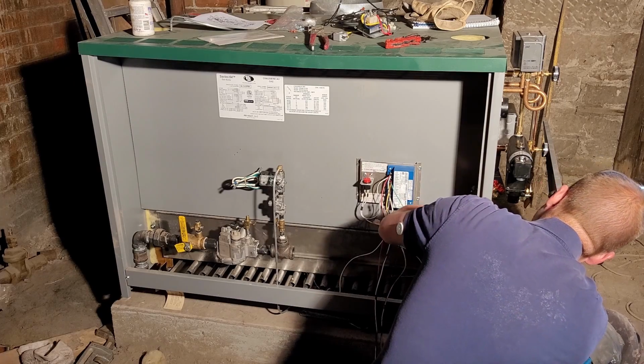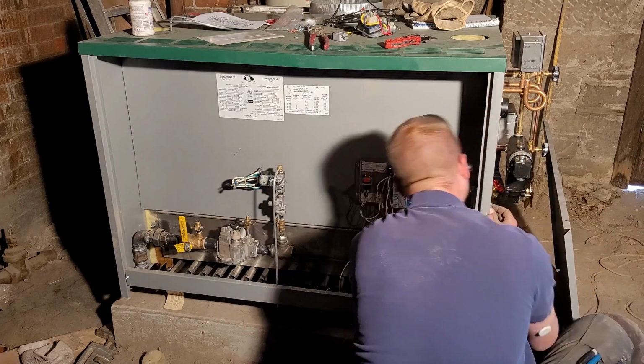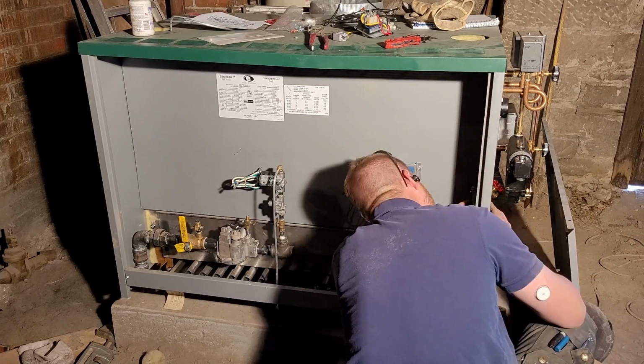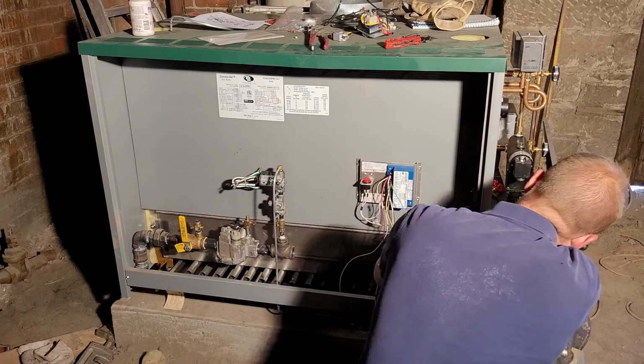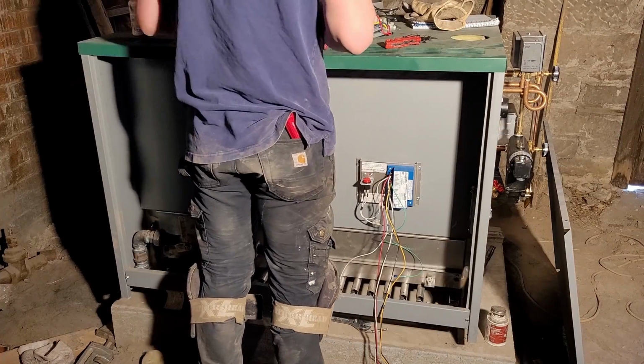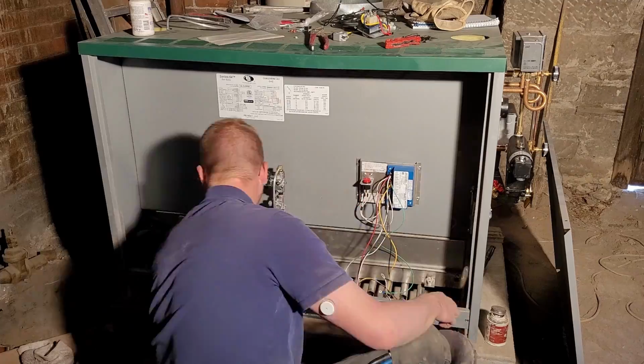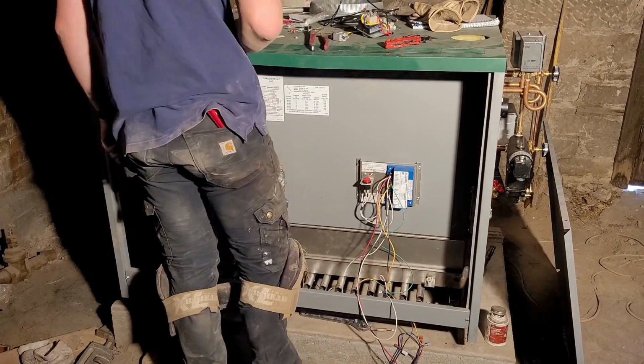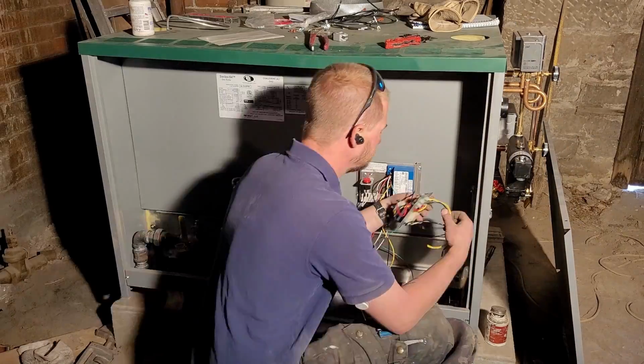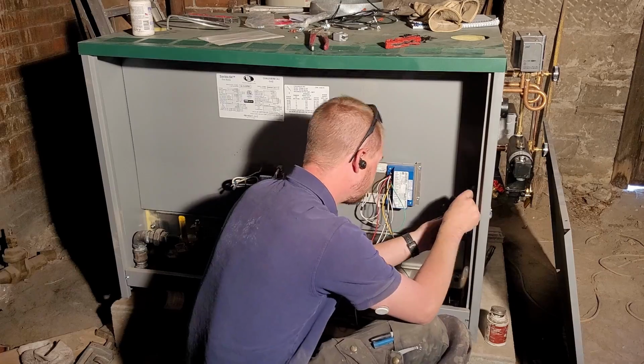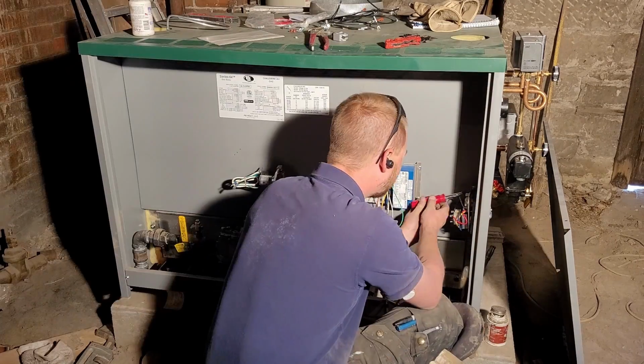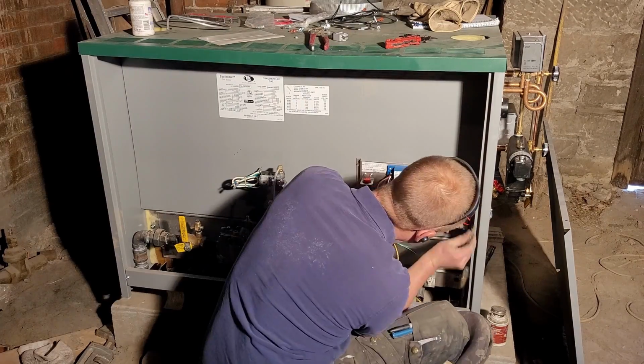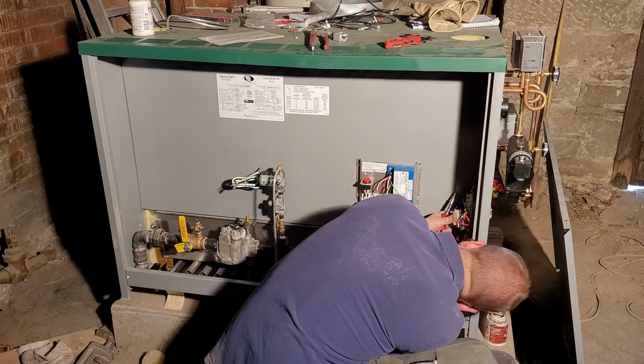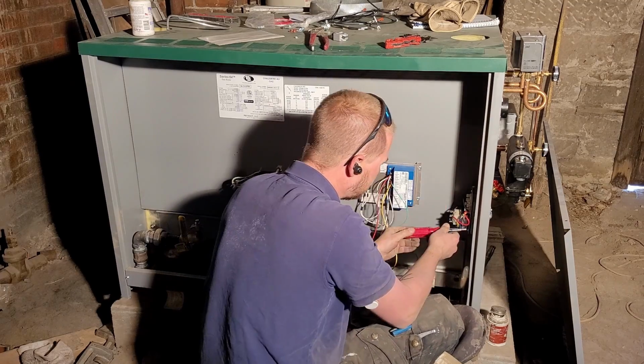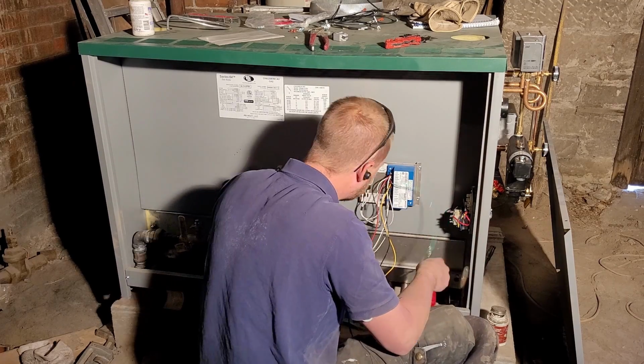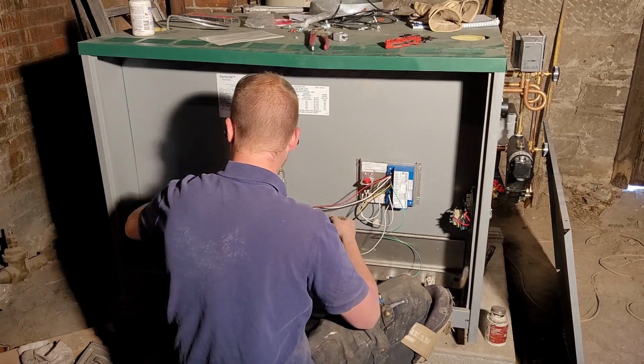And you'll see also to the left of that blue ignition module there's a big red button. What that's for is the control will sense how many times in a row it tries to fire. If it tries to light the pilot and the pilot doesn't light, or the main burner doesn't light off correctly and blows the pilot out, or anything happens like that, it will consider it a failed ignition. And there's a certain number of times it will retry by itself before it just locks out. And then someone has to come down and physically push that button to reset it and figure out what went wrong.